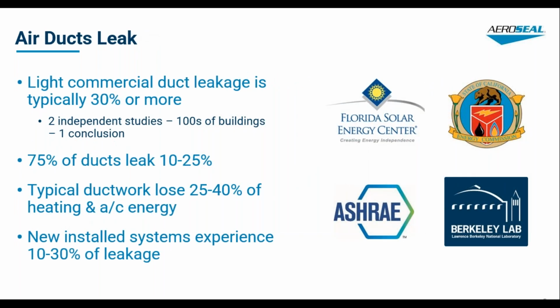Why we care about duct leakage and why it matters for your projects and buildings is because air ducts are leaky. A couple of studies, one in California and one in Florida, came to the same conclusion: commercial ductwork is especially leaky, typically more than 30%. ASHRAE tells us that 75% of ductwork leaks 10 to 25%, so pretty significant. Another study at Lawrence Berkeley Labs, the national lab, found that even newly installed systems in brand new buildings typically have 10 to 30% duct leakage. This is widespread, and it's why everything we talked about in the earlier series matters so much, because we're losing a ton of energy based on duct leakage.